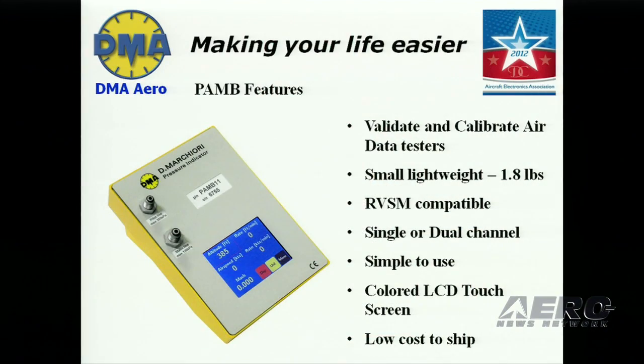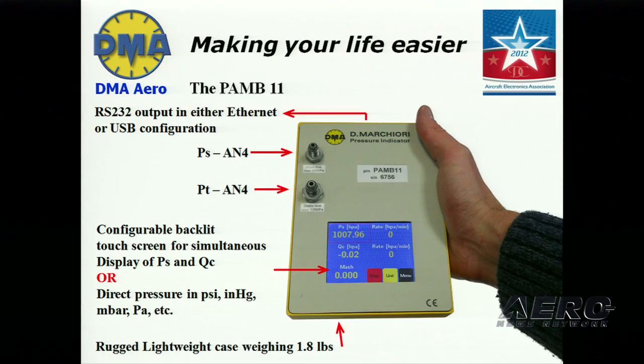The prime purpose of the PAMB is to provide validation or calibration for an air data test set, or it can be used as a NIST traceable pressure, vacuum, or barometric standard or reference. It is available in dual or single channel versions, and ranges are offered to cover all commercial aircraft requirements. Hose connections are AN4 for PS and AN3 for PT to avoid any possibility of incorrect connection, not like the slide behind me shows, which has a mistake.